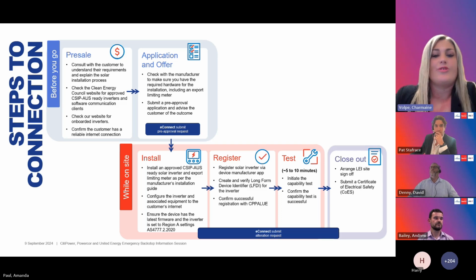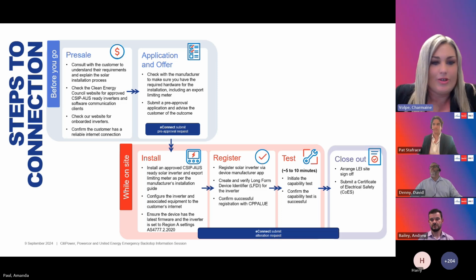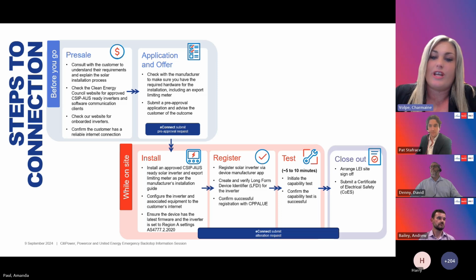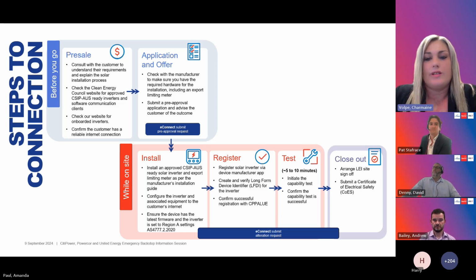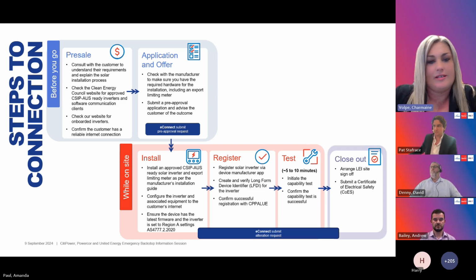Now I'll go through the while-you're-on-site stages. First, the install. You will need to ensure you're installing an approved CSIP-AUS Ready inverter and software communication client, and that you also install an export limiting meter. This is required to ensure excess energy remains within your approved export limit and that your capability test can pass successfully. Installation must be completed as per the manufacturer's installation guide.